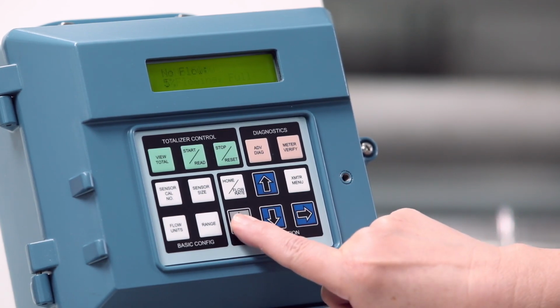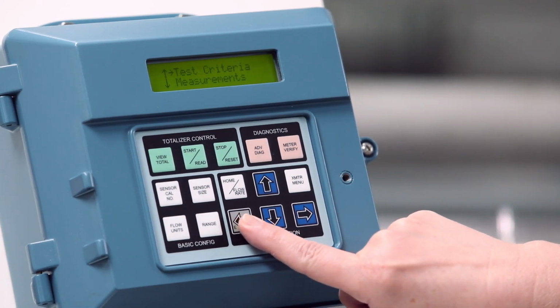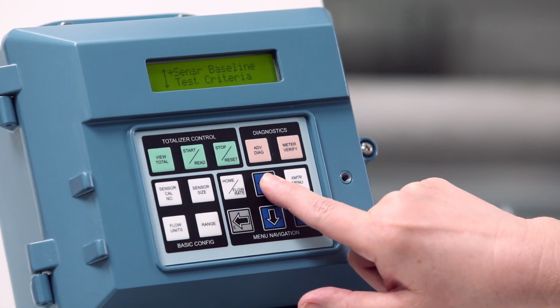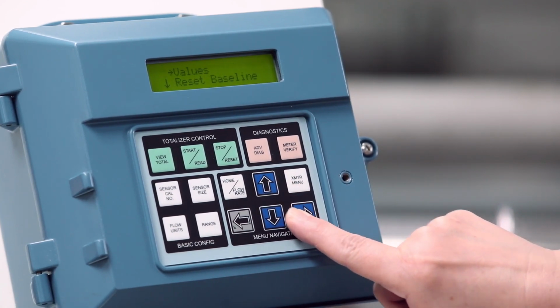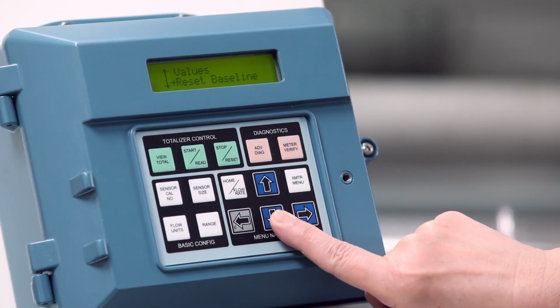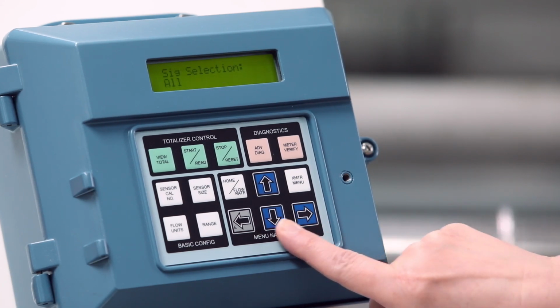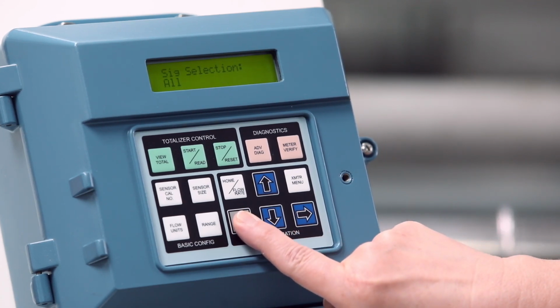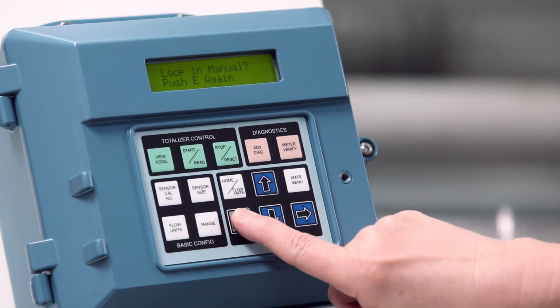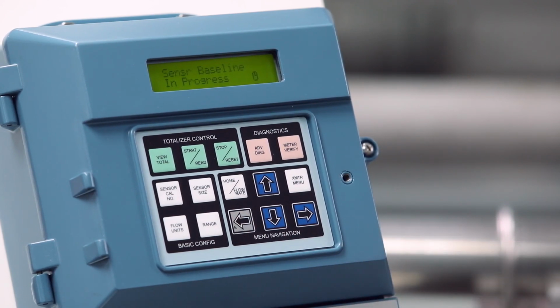Then push the E button. Next, select sensor baseline. Scroll down and select reset baseline. Push the E button to initiate the sensor baseline. It will take about 3 to 5 minutes to complete the sensor baseline. The sensor baseline is complete when the timer is no longer visible on the screen. Now you have successfully established your sensor baseline on your Rosemount magnetic flow meter.